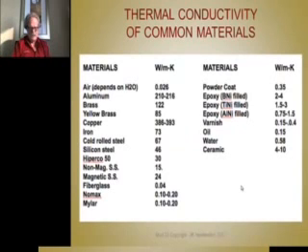Anytime you study the thermal conditions of an electric machine, it's good to have in mind what the thermal conductivity constants are for all the common materials, in particular the ones used in a motor. So we have a list here that we've compiled, and these are in watts per meter Kelvin, and this includes all of the materials used in a motor. I think it includes them all. Hope we didn't miss one. Plus it includes some other materials for reference that aren't used in a motor. I think there's a couple there. So you see there's a wide variation.